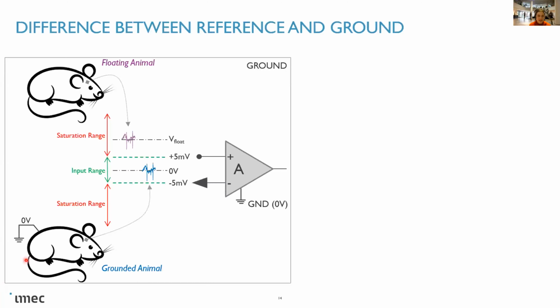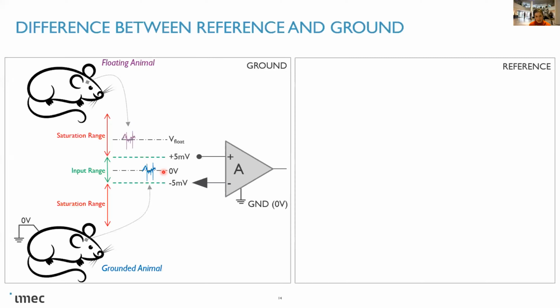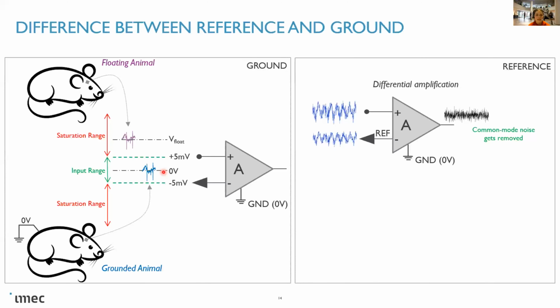So it is important that the animal is grounded to the same reference as the probe or the head stage of the system to make sure that the signal is really within the limit. So it will be centered exactly where the amplifier is expecting an input. So this is the ground. The reference is something different. The reference is a signal against which you want to do your differential amplification. So if you have common noise in your reference and in your input, basically you will have a good cancellation of your common mode noise and only record the signal that matters.